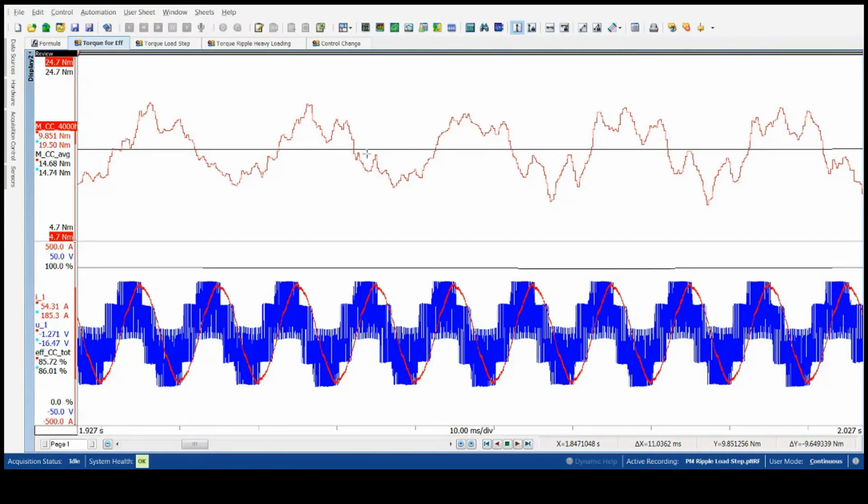and valleys. We can use the instantaneous torque to get a power value, but typically what is desired from these efficiency scenarios is a good average that is on the same time basis as the average used for RMS voltage and current. Having a common time average for electrical and mechanical values gives us a good efficiency without inaccuracies being introduced from natural fluctuations of the system itself or outside fluctuations of a dyno.